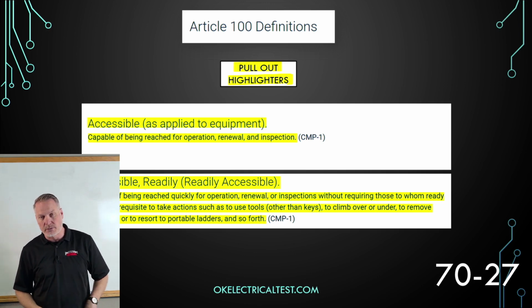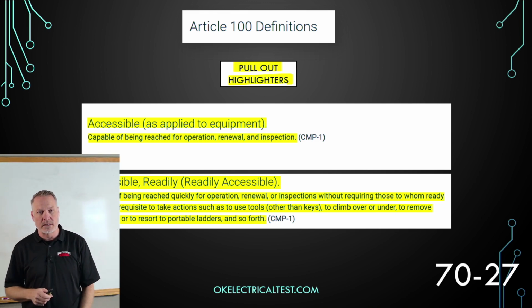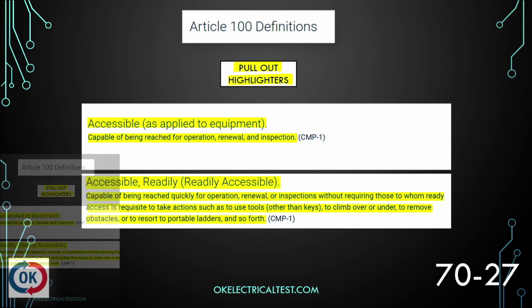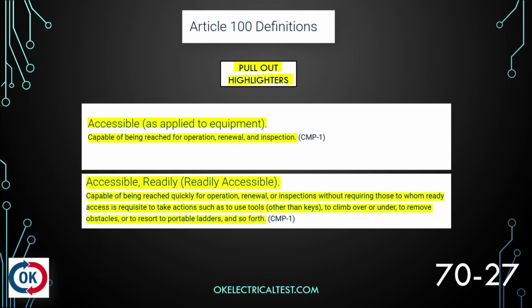So we're going to start off here with accessible, and this is accessible as applied to equipment. That's capable of being reached for operation, renewal, and inspection. So if something is capable of being reached for operation, renewal, and inspection, that's going to be considered accessible. But there's also this term readily accessible. And so that's a little bit different, a little bit more nuanced. And so readily accessible, that's capable of being reached quickly for operation, renewal, or inspections without requiring those to whom ready access is requisite to take actions such as tools to use other than keys, to climb over or under, or to remove obstacles or resort to portable ladders and so forth.